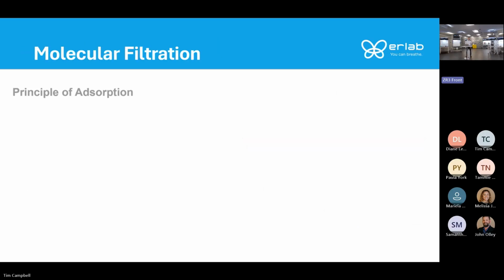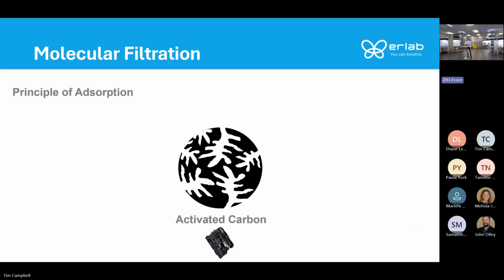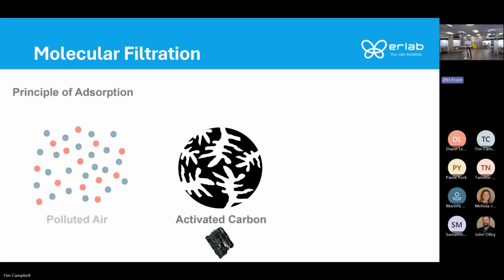So to show you just the basis of how molecular filtration works, or the principle of adsorption. You have your activated carbon, so that's in the carbon filter on top of the hood. The hood's running. You're creating polluted air in there. You're creating chemical vapors. So the blue is just lab air being pulled into the hood. The red, those are those chemical vapors you're creating.